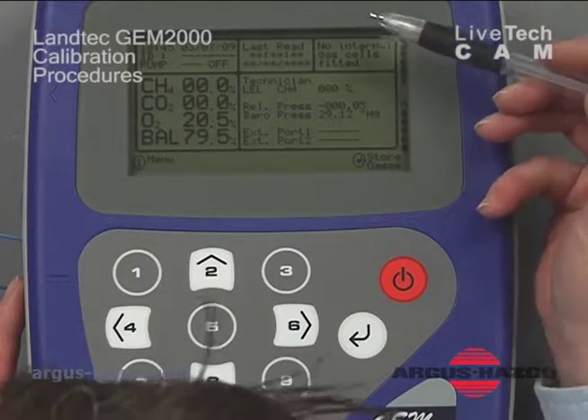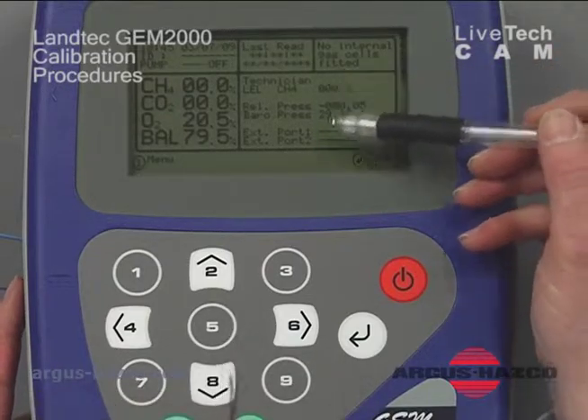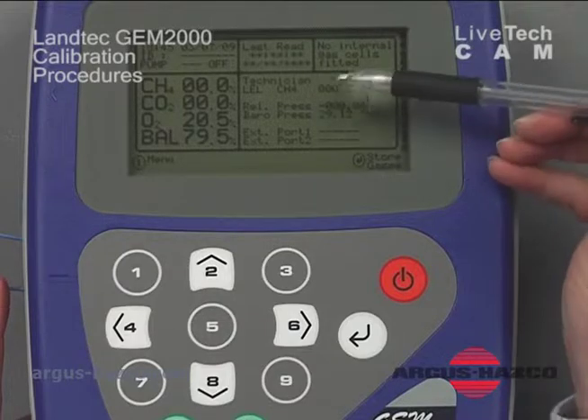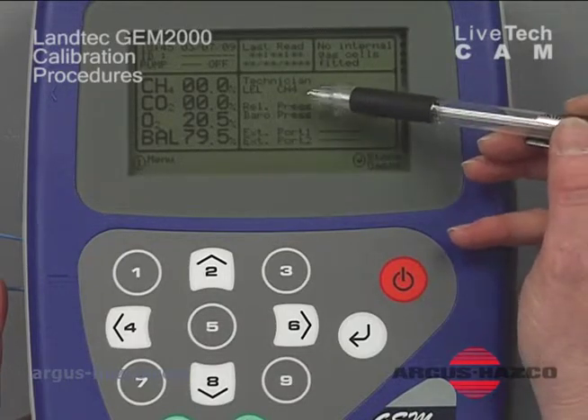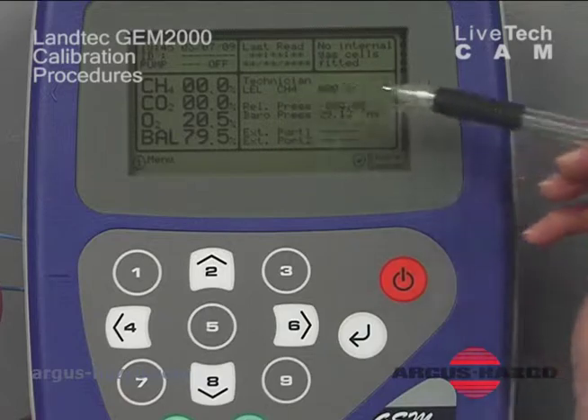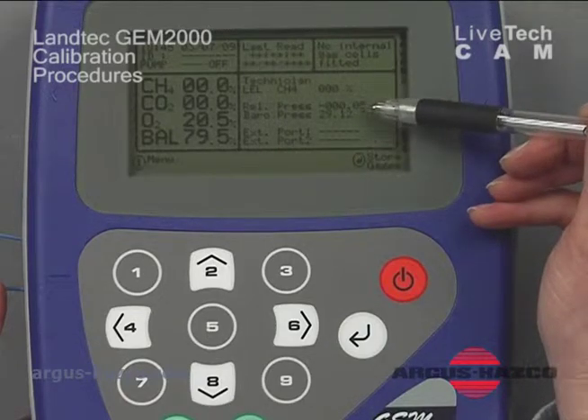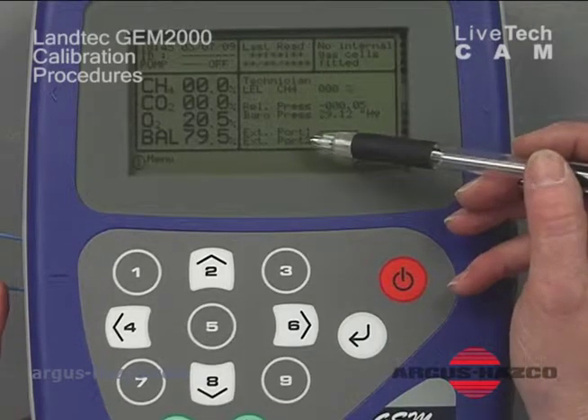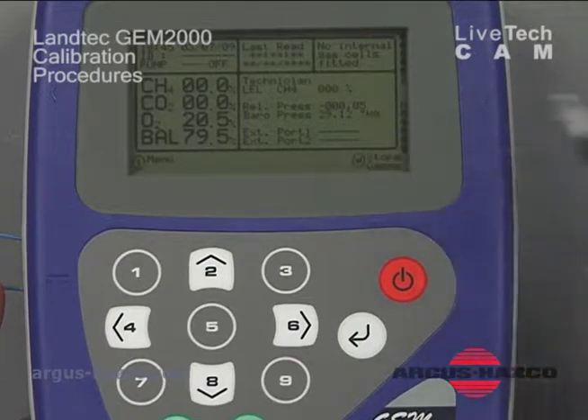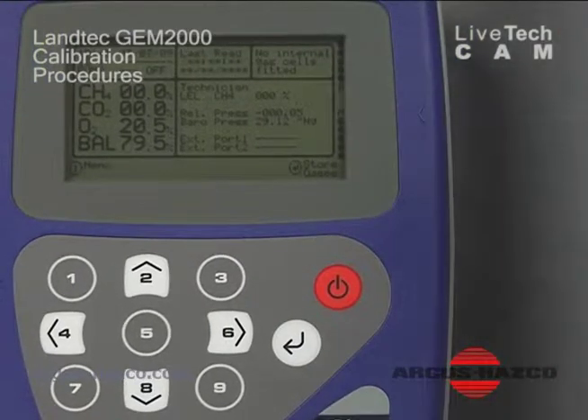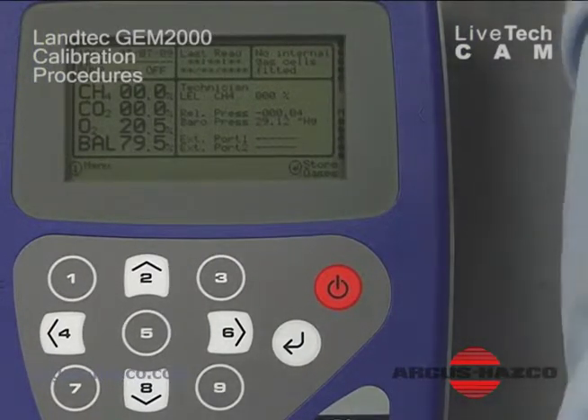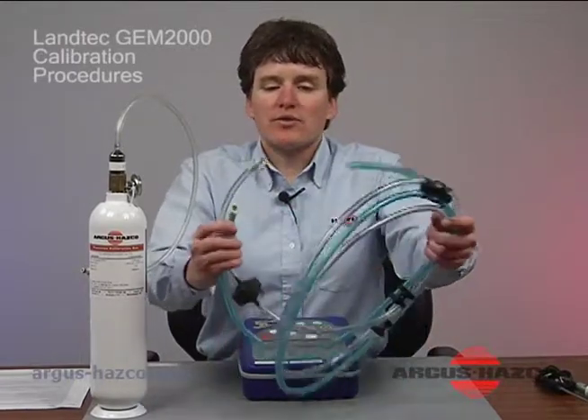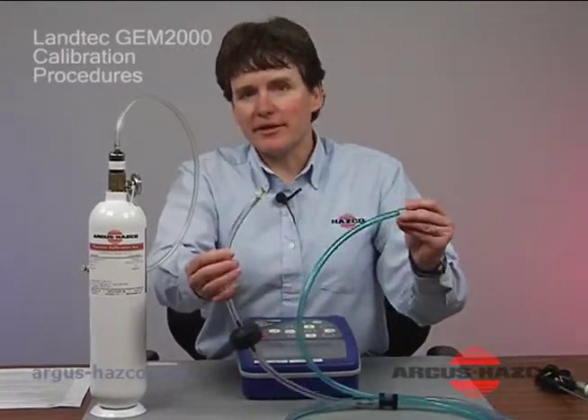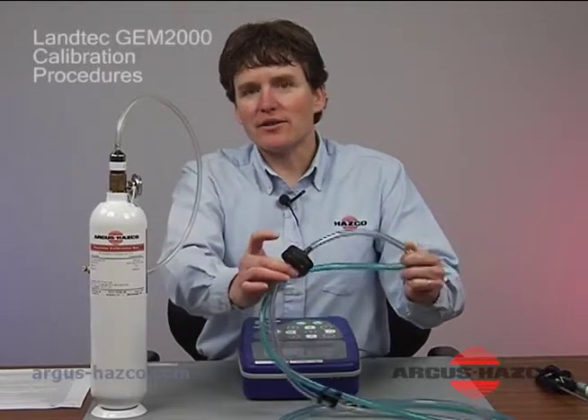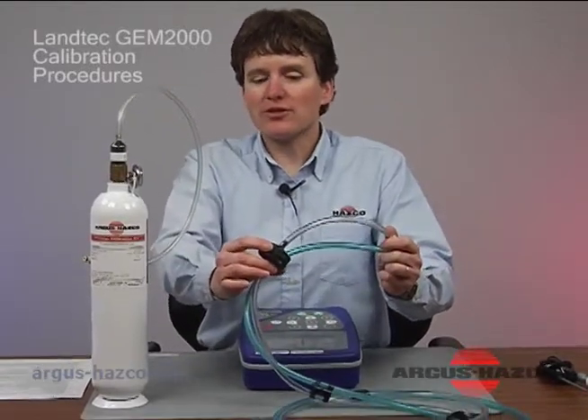Off to the right of the screen, it gives you more information. Gives a technician name, your methane in LEL %, and it will also give us our pressure readings, and if we have any exterior port probes connected, what those probes are reading. One thing I do want to point out at this point in time is the tubing that you will receive with the unit. You'll notice one tube is blue and the other tube is clear, and the clear tube has our moisture water trap attached.